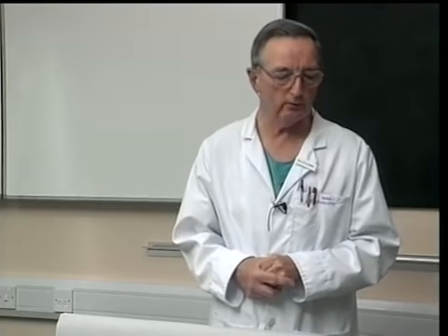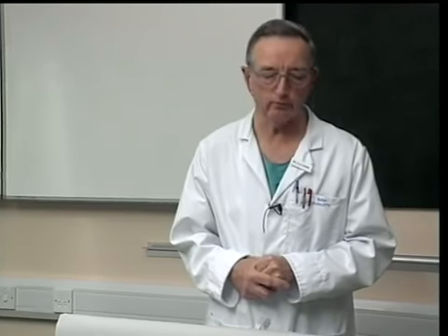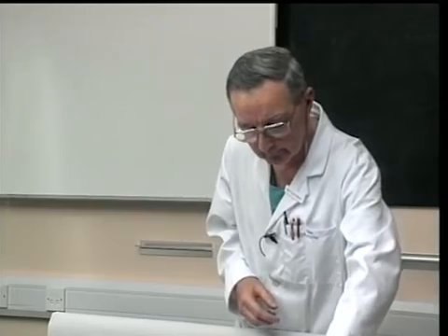But before these catheters had been in use for very long, several cases of cauda equina syndrome were reported to the FDA in America. That's the Food and Drug Administration. And I'm going to show you what may happen. I have here a 28 gauge catheter, and I'm going to use a 1 ml syringe for the injection because you need that sort of pressure to get the local anesthetic solution down the catheter.